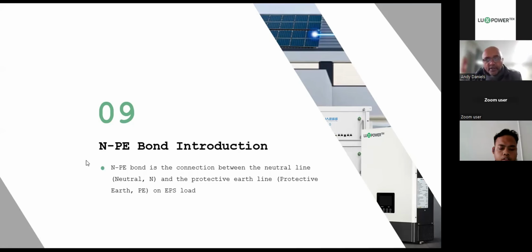So we might have TN-C or TN-S, but typically we have TN-C here, where earth and neutral are combined. Your feed from the grid is normally bonded from the transformer to the house, and you'll know that when you measure voltage on the incoming grid between neutral and earth, you should get 0 volts. Okay, if there's voltage there, then it simply means that the neutral earth bonding has been compromised, and you need to notify the utility supplier.